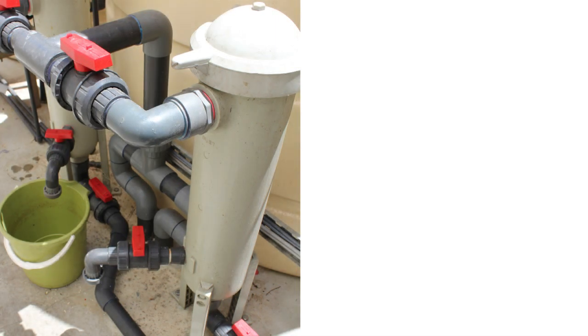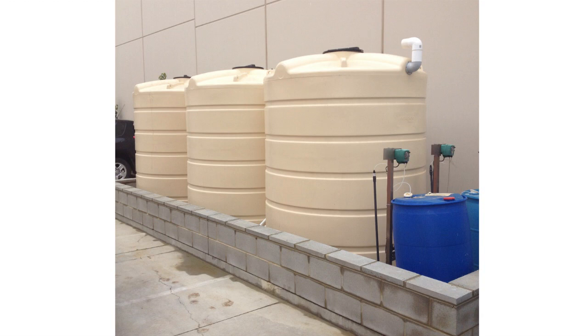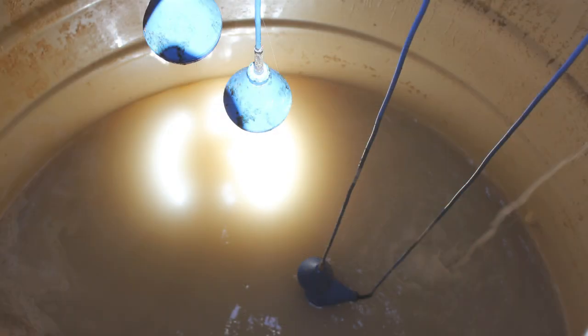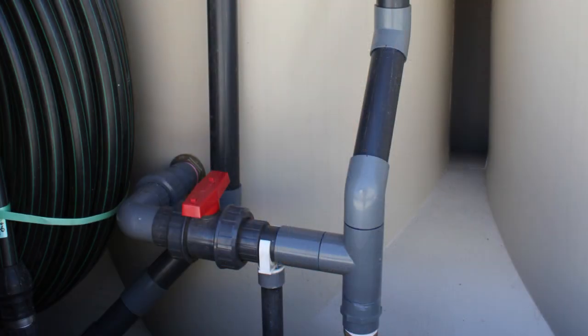The pumped wastewater is screened in pressurised screens fitted with removable disposable screening bags. The wastewater discharges into a blending tank where it's mixed and corrected for pH. Wastewater from the blending tank flows to a flow balancing tank, and is then pumped to the AeroFloat DAF at a rate of 3,500 litres per hour via flocculation coils.